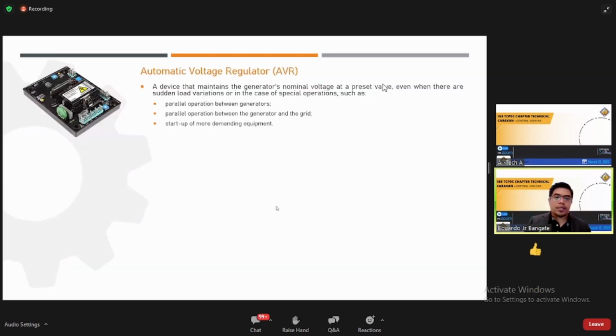Okay, let's see. This is our example of the automatic voltage regulator, AVR. This is a device that maintains the generator's normal voltage at a preset value, even when there are sudden load variations or in the case of special operations, such as parallel operation between generators, parallel operation between generators and the grid, start-up of more demanding equipment.